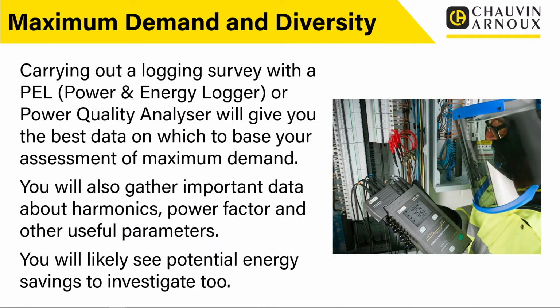So carrying out a logging survey with a PEL, a power and energy logger, or power quality analyzer will give you the best data on which to base your assessment of maximum demand. You will also gather important data about harmonics, power factor, and other useful parameters. You will likely see potential energy savings to investigate too.